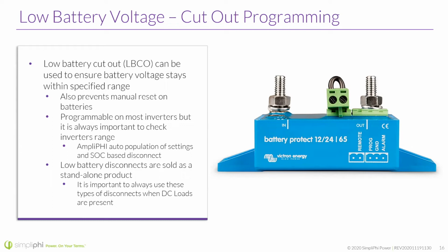The AmpliPHI battery, our newest comms based battery, does auto populate SOC based disconnects, meaning it doesn't need low battery voltage. It automatically knows how to calculate its state of charge based on percentage and voltage internally. So it does all that guess and check work for you. And it will always go into a low battery protection mode if needed.